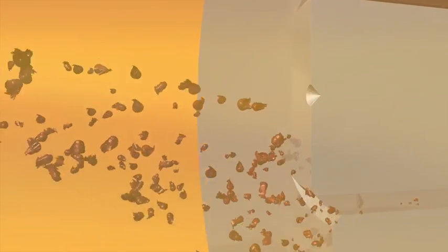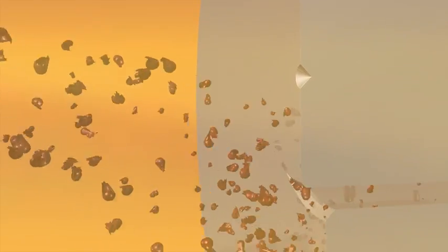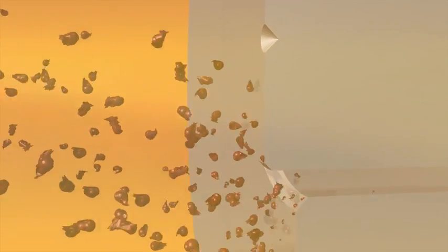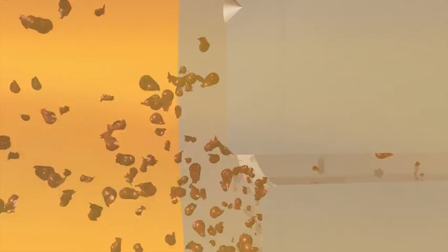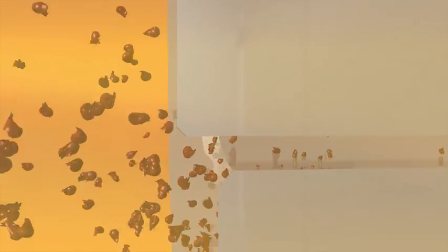Once inside the tolerance, they get stuck at the finest clearance and damage the metal surface leading to surface erosion and increased particle production. And if not stopped in due time, the gearbox breaks down.